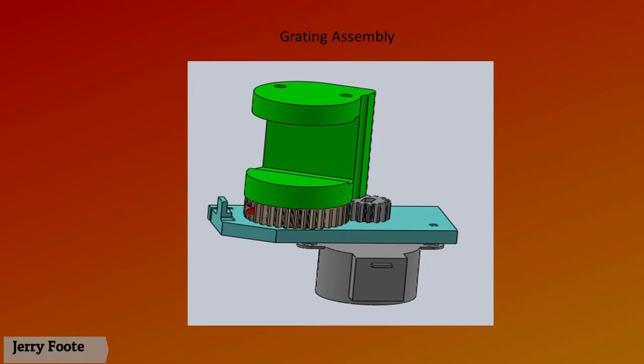There's a stepper motor with a gearbox on the bottom outside the case. There's a small pinion gear and then a main driven gear. Also notice we've retained the ability to swap out gratings by magnetically coupling them to the main driven gear. Thus you can change the grating line frequency by just changing out the grating.